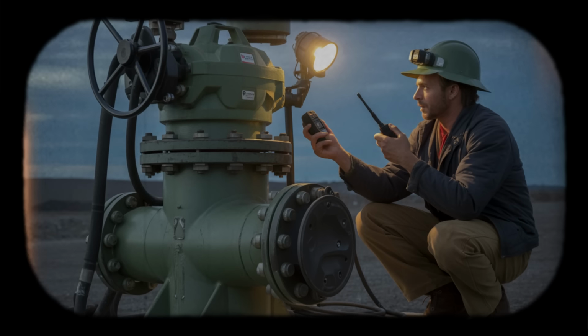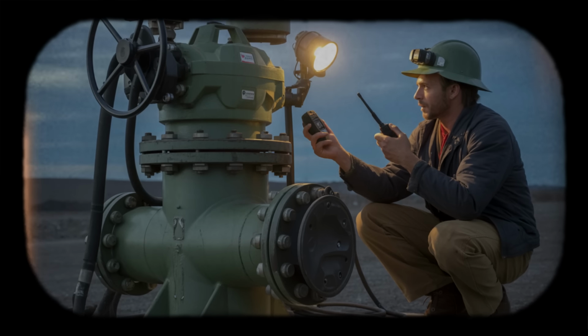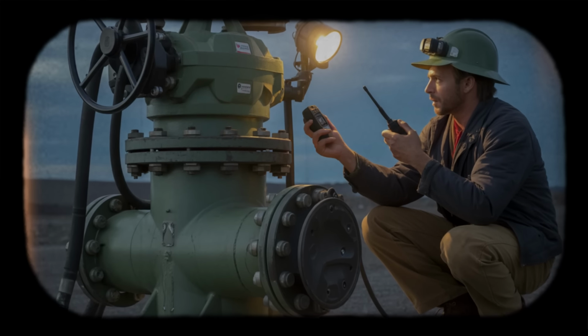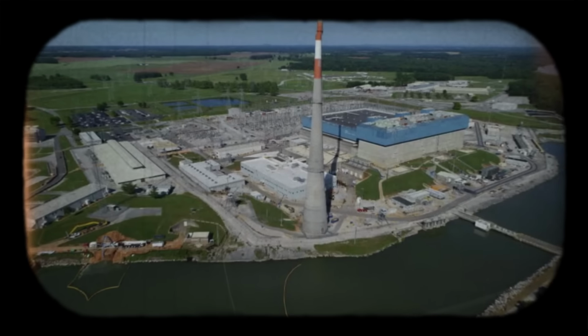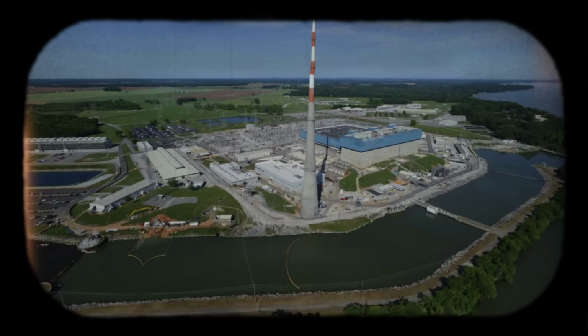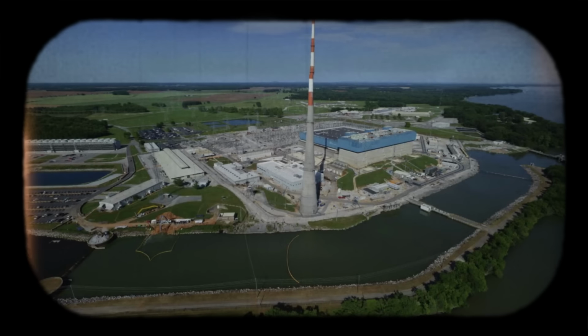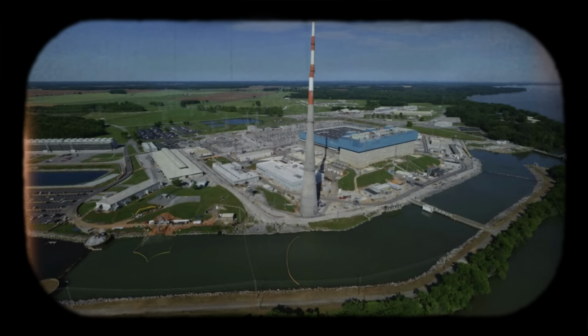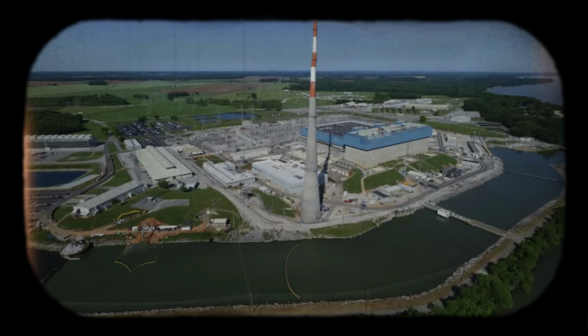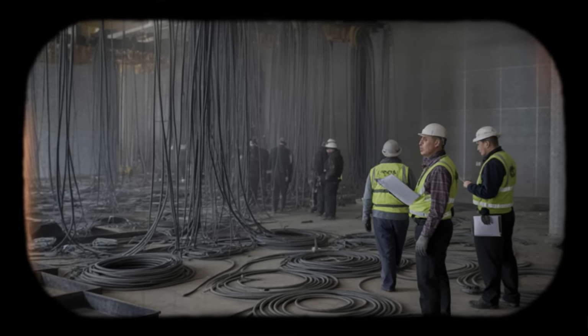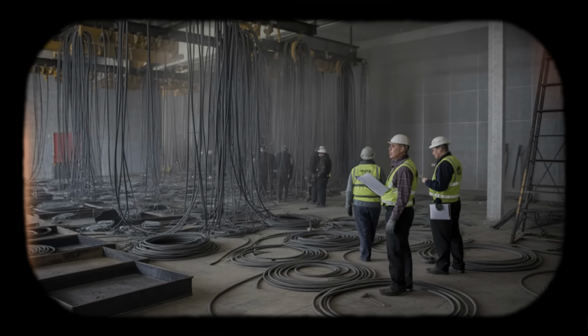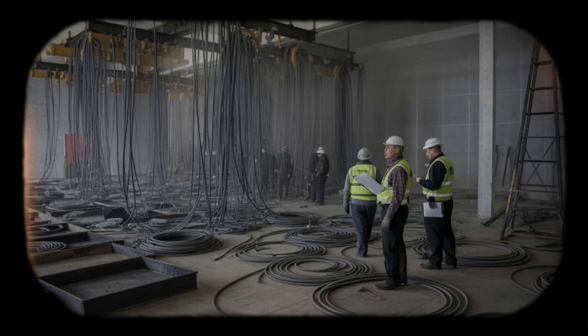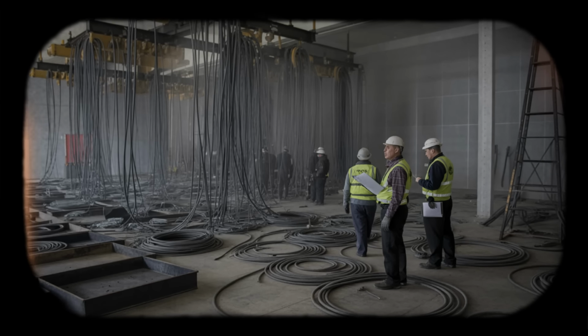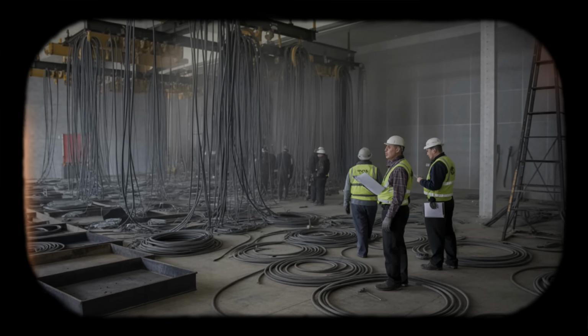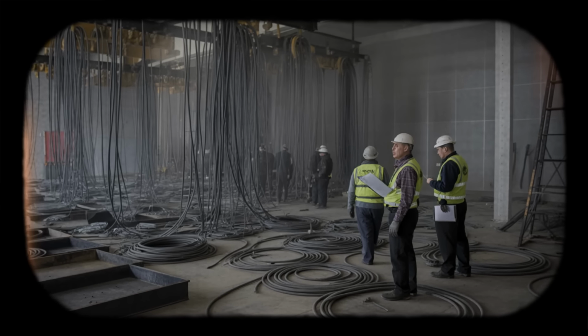Improved fire detection and suppression systems are required throughout the plant. Areas containing safety-related equipment or cables must have automatic detection that alarms in the control room and activates suppression systems. Suppression systems must be designed to control fire without causing unacceptable damage to safety equipment. This leads to widespread installation of automatic sprinklers, deluge systems, and gaseous suppression systems using halon or carbon dioxide. Industry-wide redesign of penetration seals begins. The foam seals that allowed fire to spread at Browns Ferry are systematically replaced with fire-rated seals at every nuclear plant. The NRC issues generic letters and bulletins directing licensees to inspect existing seals, test them if possible, and replace any that do not meet new fire-resistant standards.